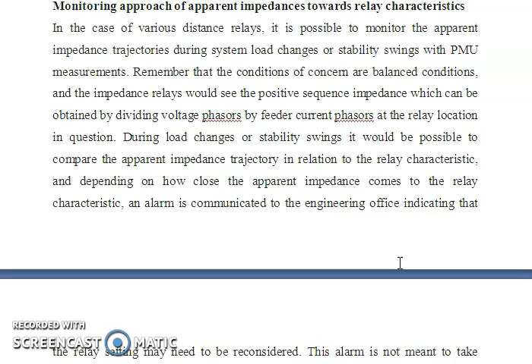Now another application of the wide area measurement system is monitoring the approach of apparent impedance towards relay characteristics. For this topic we have already discussed power swings and their effect on distance relays. In the case of various distance relays, it is possible to monitor the apparent impedance trajectory during system load changes or stability swings with PMU measurements. Remember that the condition of concern is the balanced condition, and the impedance relay would see the positive sequence impedance, which can be obtained by dividing the voltage by the current at the relay location.